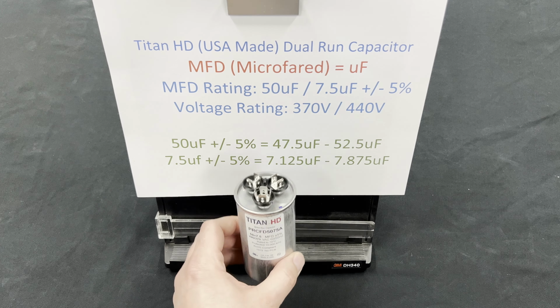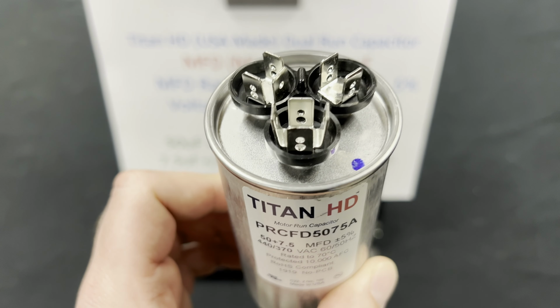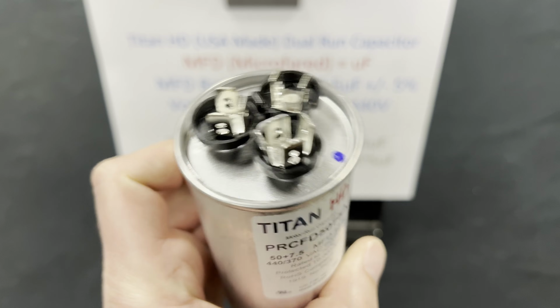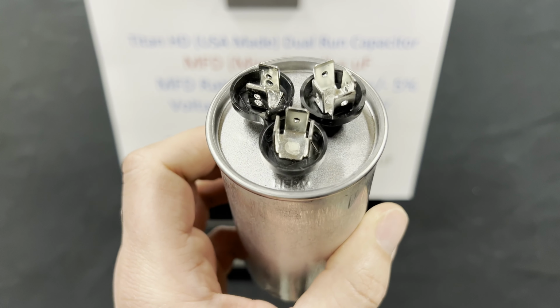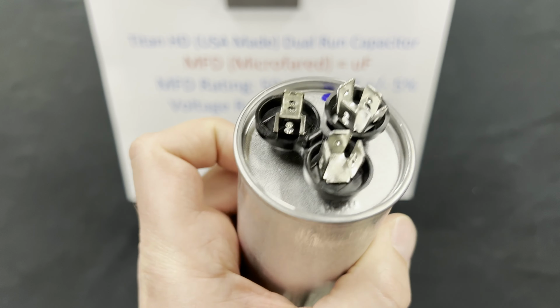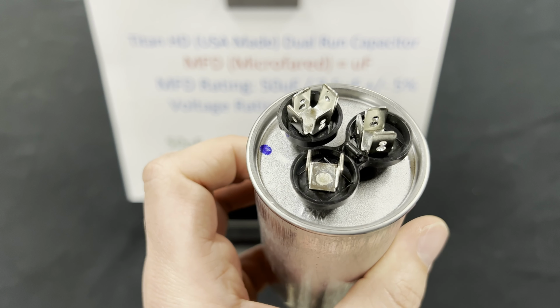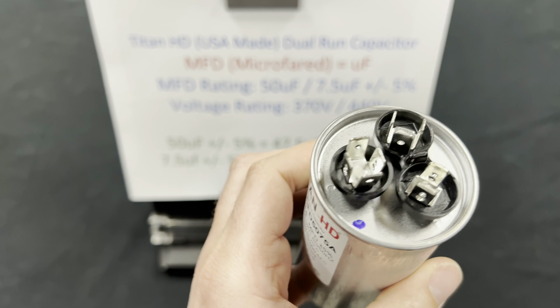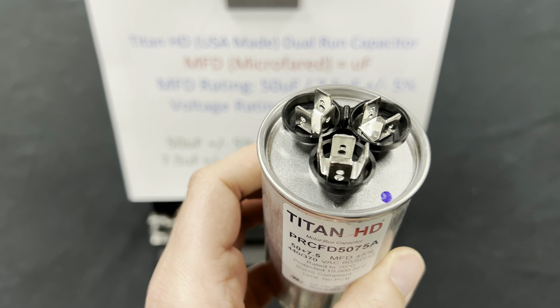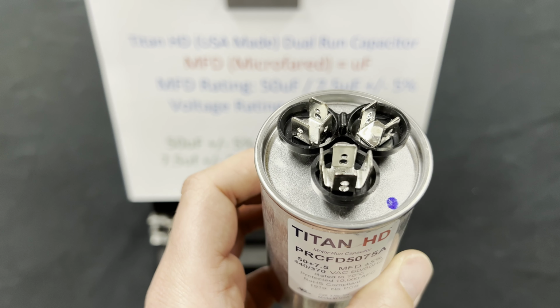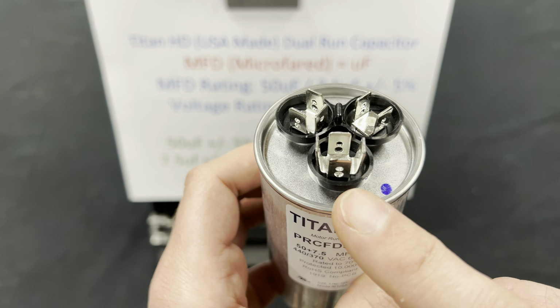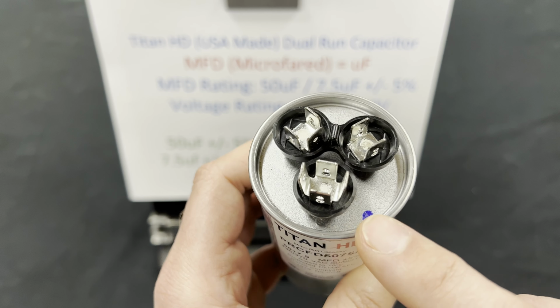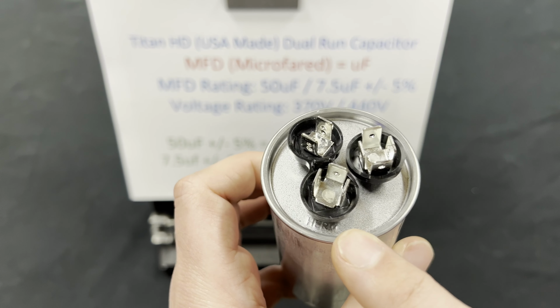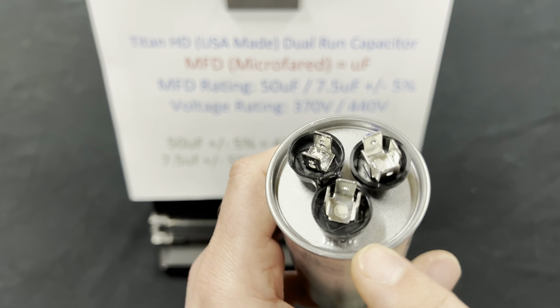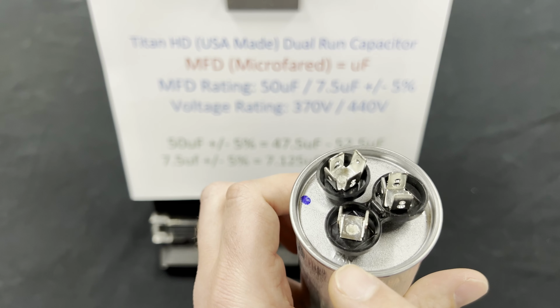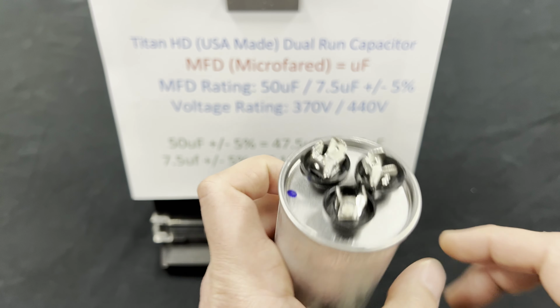A dual run capacitor consists of three terminals on the top. One labeled C for common, one labeled Herm for hermetic, which means it's the compressor, and one labeled fan, which is for the condenser fan motor. If you have a capacitor where you're unable to see the markings on it, a tip is that a common will have 4 connectors on the top of it. A compressor or hermetic will have 3 connectors on the top of it, and a fan will have 2 connectors on the top of it.